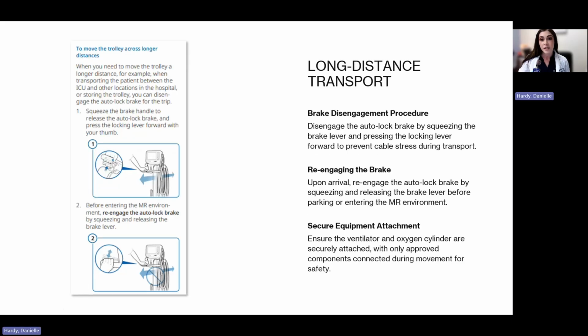For longer transport, such as moving the ventilator between hospital departments or to storage areas such as MRI, or going down the hall or leaving the ICU with the patient, the auto lock brake should be disengaged to prevent cable stress. Begin by squeezing the brake lever to release the brake. Then press the locking lever forward with your thumb to keep the brake disengaged during the trip. This prevents continuous tension on the brake cable, which is a common cause of mechanical failure.